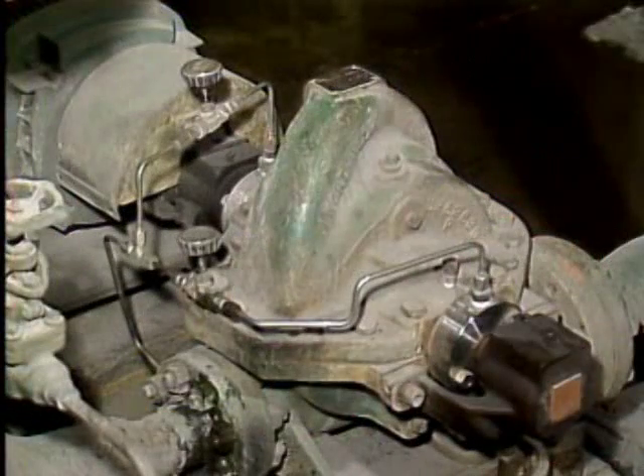As an operator, you may be responsible for the proper operation of many pumps. To ensure that they're operating properly, you need to know what to look for to identify potential problems. We're going to look at 3 components associated with centrifugal pumps and at some of the indications of problems associated with these components. Let's start by looking at packing and mechanical seals.